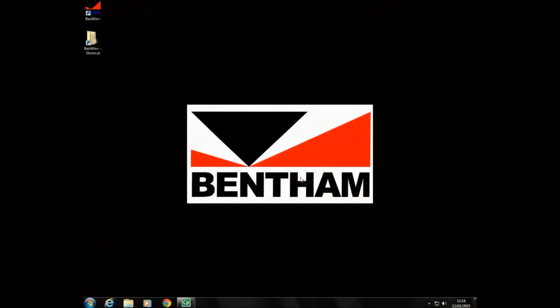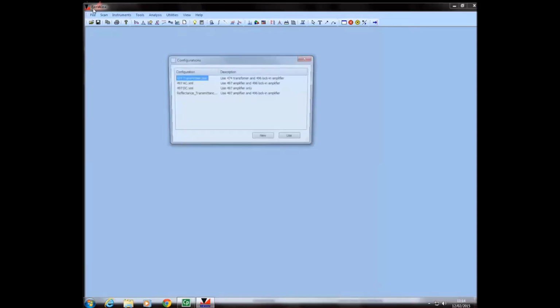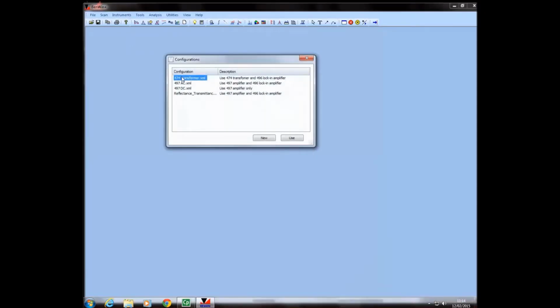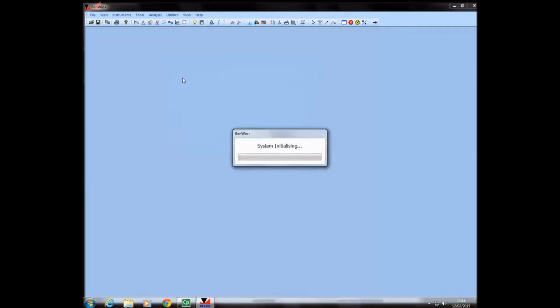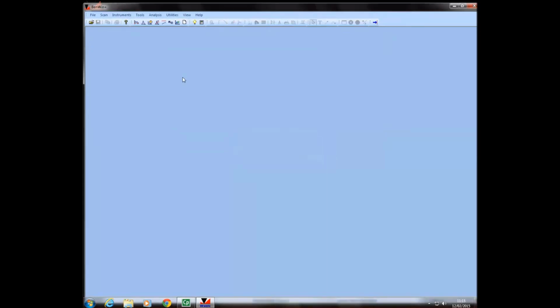So now, ensuring that all of the elements of the PV300 system are powered on and connected to the computer via USB as required, we shall run BenWin+ from the desktop and initialize in the 474 transformer mode by double-clicking. The system initialization process will move the turret and the filter wheel in the monochromator to a fixed reference point, and also move the motorized stages to their reference position.